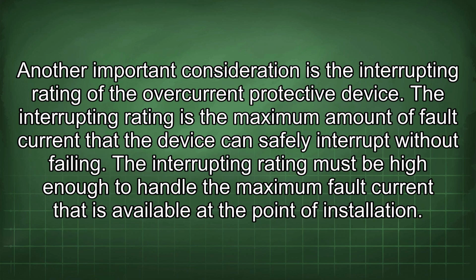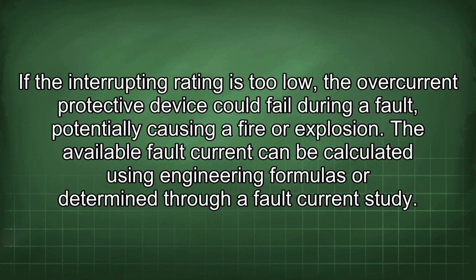Another important consideration is the interrupting rating of the overcurrent protective device. The interrupting rating is the maximum amount of fault current that the device can safely interrupt without failing. The interrupting rating must be high enough to handle the maximum fault current that is available at the point of installation. If the interrupting rating is too low, the overcurrent protective device could fail during a fault, potentially causing a fire or explosion. The available fault current can be calculated using engineering formulas or determined through a fault current study.